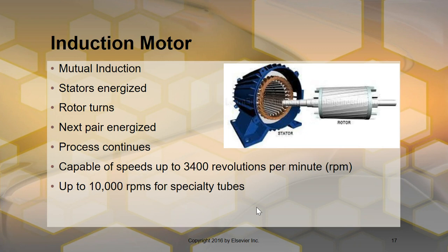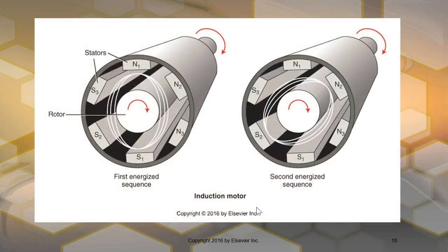The more it moves, the more heat it can disperse, and the better your imaging will be. This is just another induction motor. Here's the first sequence, then here's the other, and then there are your stators that are keeping it from spinning off into space. So it allows for the rotation of the anode in a vacuum, and I've already told you how fast they can go.